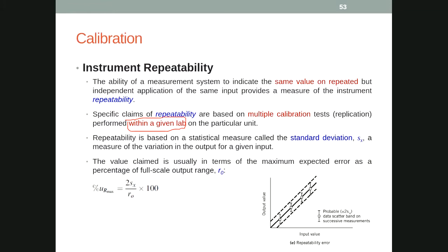Finally, calibration, repeatability, and reproducibility. We will see. So what does this mean? Precision. We already discussed that precision means we will perform multiple duplicate, replicate tests: one test, two tests, three tests, four tests, fifth test, sixth test, seventh time, and we will see how much they are close to each other. So basically, repeatability and reproducibility are both checking the precision. There are some things that are common between them, and there are some differences.